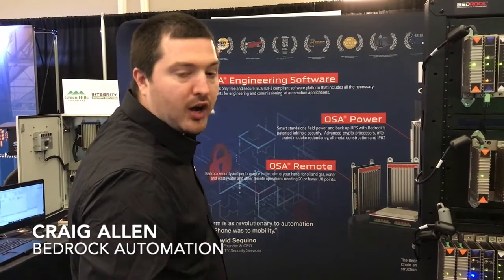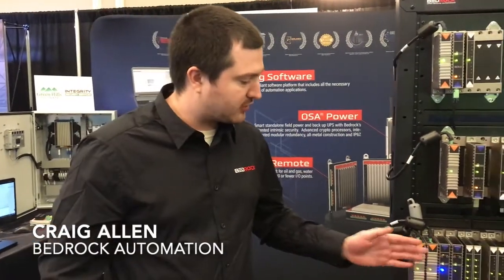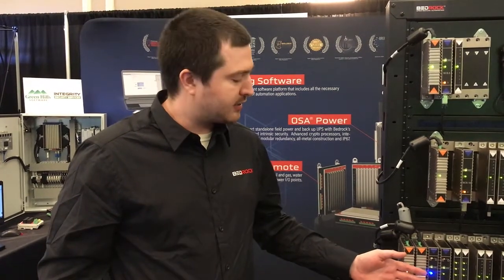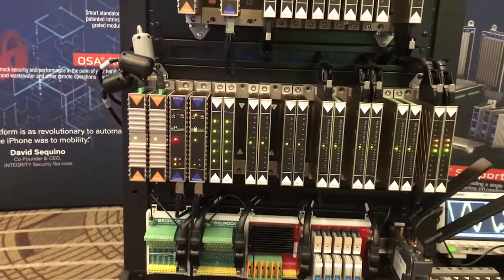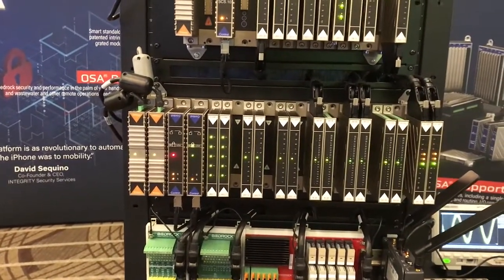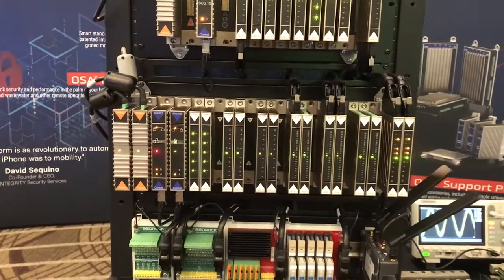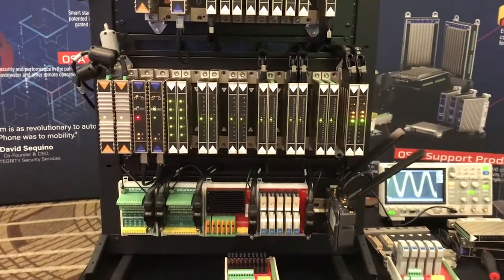Okay, as we just completed the firmware update on the operator station, you'll notice as the controller comes in, you'll first see the controller power cycle. It'll go into a red state and start doing its reboot process. At that point, you'll notice the lights change from the primary to the secondary controller, with the secondary controller taking over as the new primary controller.